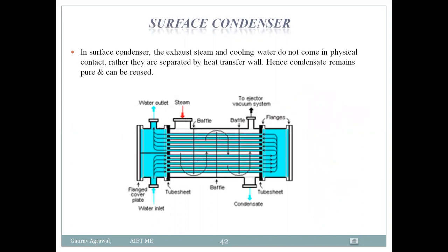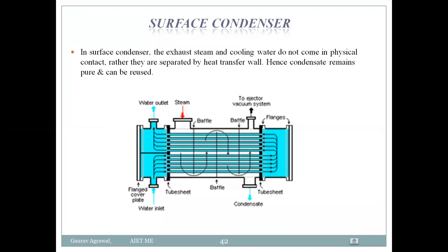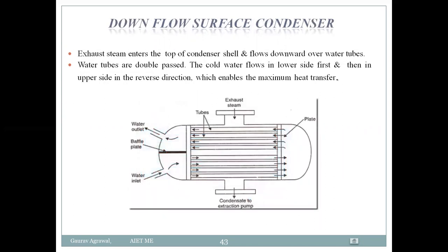Next is the surface condenser. In surface condensers, pipes separate the hot fluid and cold fluid — the condensate and cooling water do not mix. Different configurations are possible using pipes and baffle plates. The first type is the downflow surface condenser, where exhaust steam enters and flows downward. Water flows through tubes, and condensate is collected and removed by extraction pumps, with baffle plates used to separate flows.